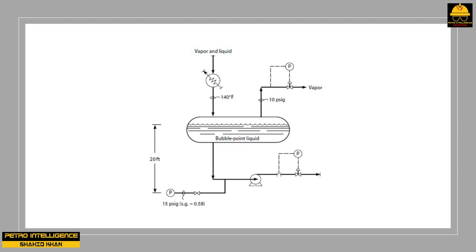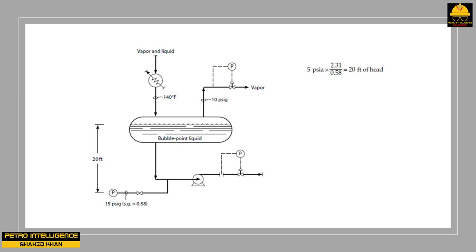The physical pressure at the suction of the pump is measured at 29.7 PSIA — 15 PSIG plus 14.7 PSIA of atmospheric pressure. The physical pressure at the suction of the pump, 29.7 PSIA, minus the vapor pressure of the liquid, 24.7 PSIA, equals 5 PSIA. To convert to feet: 5 PSIA times 2.31 divided by 0.58 specific gravity equals 20 feet of head.